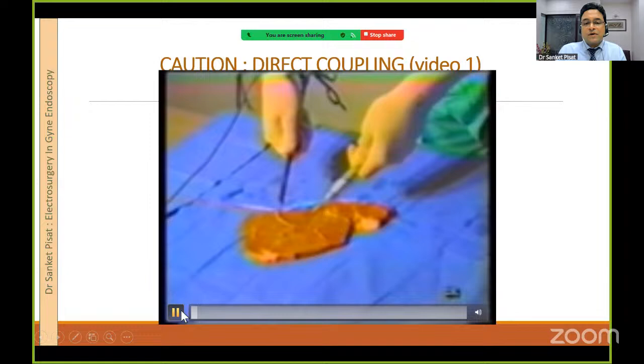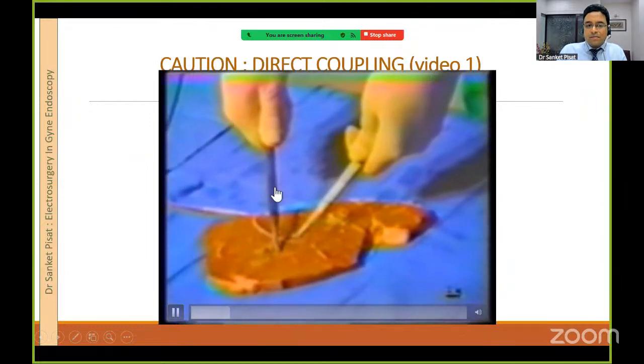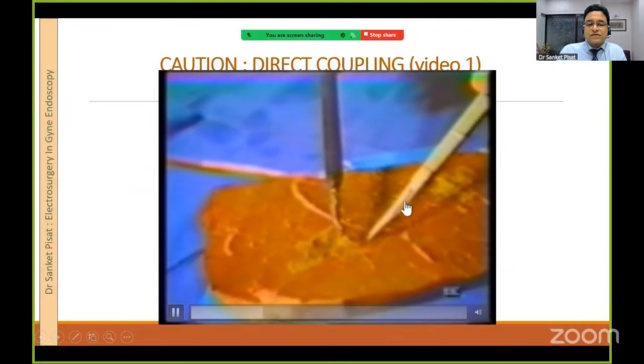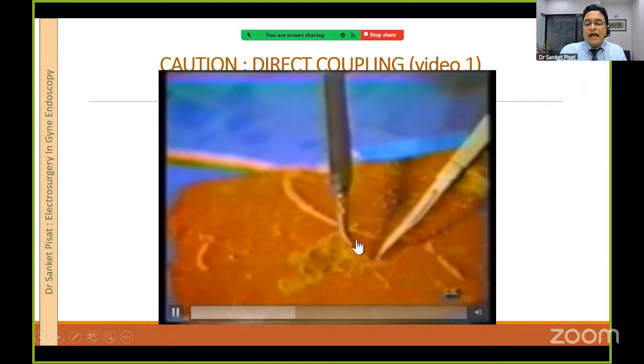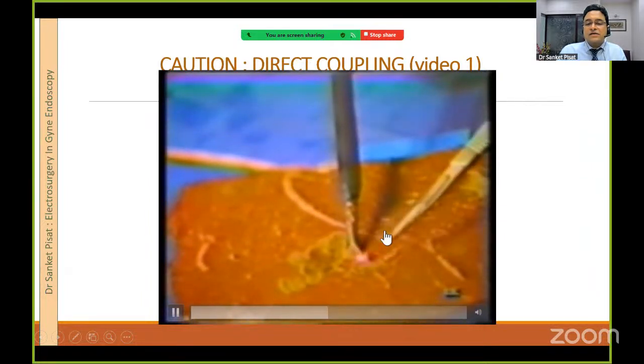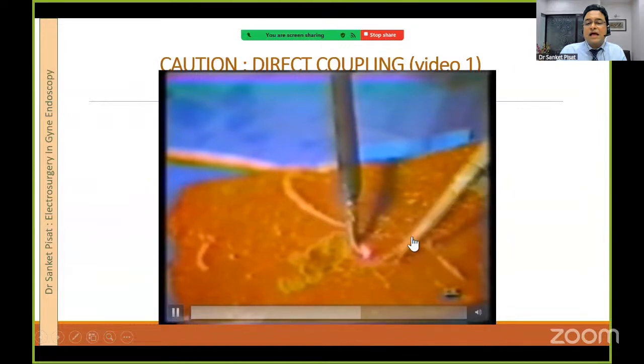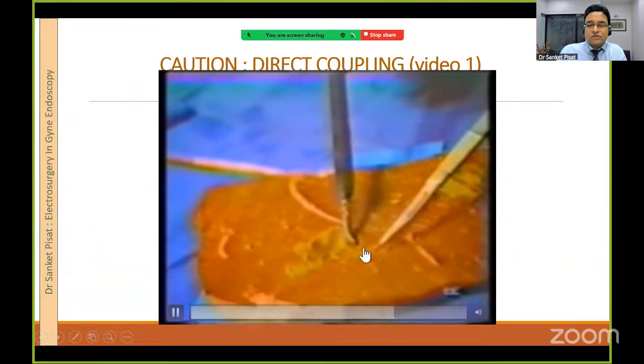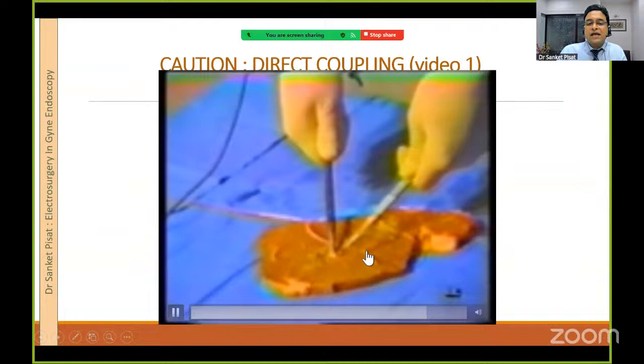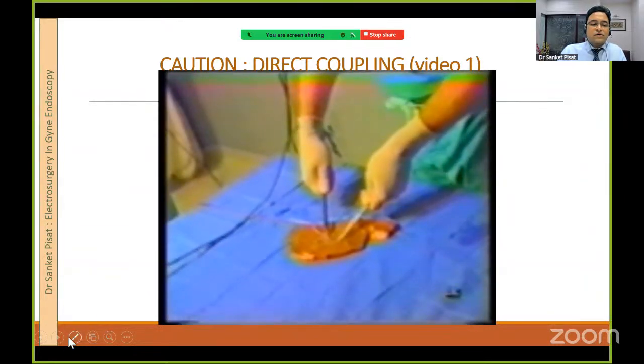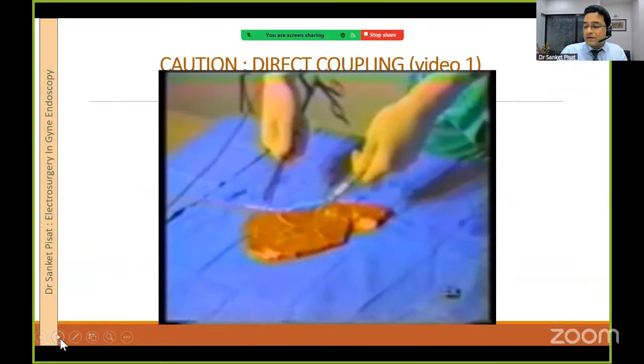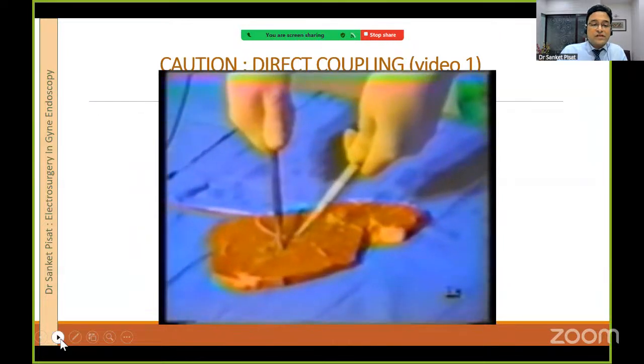Right, okay, so you can see this is an example of the same thing. This is a monopolar electrode. This is a scalpel, which is obviously not connected to anything. And without doing anything, the current is jumping from here to the scalpel and then going back to the return electrode. So this can actually happen during surgery if the current is strong enough and the two metallic instruments are in close proximity with each other.